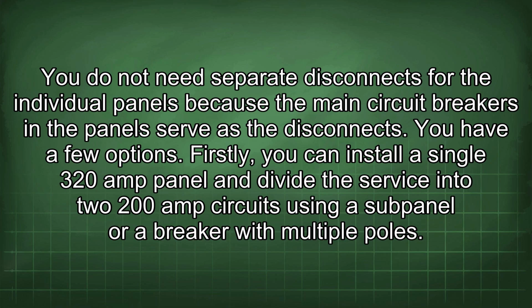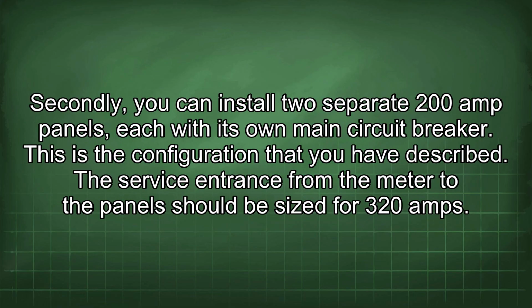Firstly, you can install a single 320 amp panel and divide the service into two 200 amp circuits using a subpanel or a breaker with multiple poles. Secondly, you can install two separate 200 amp panels, each with its own main circuit breaker. This is the configuration that you have described.